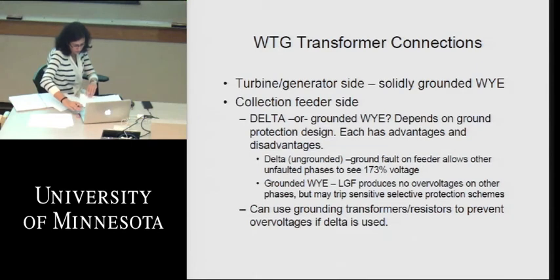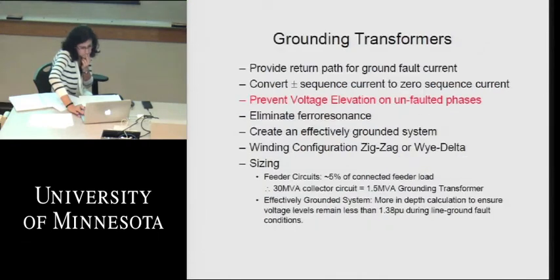If you pick a delta, one of the good sides is that it doesn't allow zero sequence components to flow through the transformer. But on the downside, if you've got a single phase ground fault, you might see as high as 173% overvoltage on the two healthy phases. If you went with a grounded Y, you wouldn't see those overvoltages, but it's much trickier to provide selective coordination between the different protection devices, from the grid to the collection bus to the feeder bus all the way out to the wind turbine. It makes it much harder to coordinate all that and get them to not accidentally trip, or inadvertently trip in a manner that is not exactly how you want them to. So you pick one or the other and you have to go with it. But if you're using deltas, then we generally use these grounding transformers here.